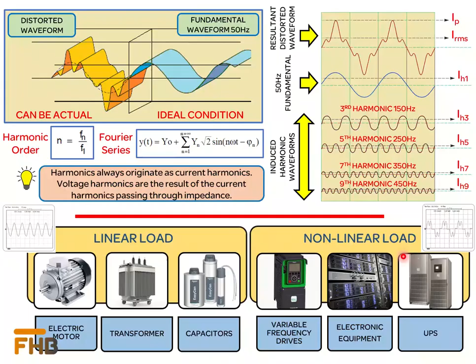The loads connected in the power system can be classified as linear loads and nonlinear loads. A load is said to be linear if its waveform remains a sine wave. Many types of loads fall under linear load, such as electric motors, transformers, capacitors, and resistive heating elements. Industrial equipment based on power electronic circuits is considered nonlinear load. Examples are variable frequency drives for electrical motors, electronic equipment such as PCs, printers, servers, etc., and the UPS. Other common industrial equipment such as welding machines and battery chargers also produce harmonic currents, which when passed through the system impedance cause voltage distortion.